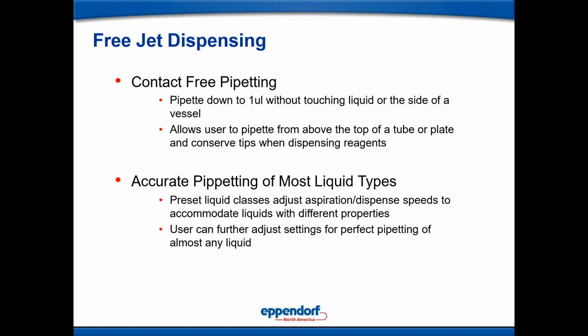Many machines can't do this because of the way that they do the aspirations. They have system liquids and peristaltic pumps that simply cannot do this. So our machine can do this. It will automatically build in a certain amount of additional air volume for the liquid class. It'll pick up the air stroke. It'll start the piston farther back and then back up as it aspirates the liquid, then goes to the receiving well. It does pull a trailing air gap to prevent expansion or dripping from occurring as it moves across the deck. But then it closes down that trailing air gap, spits out the desired volume, and then pulls another trailing air gap before it moves to the next location.